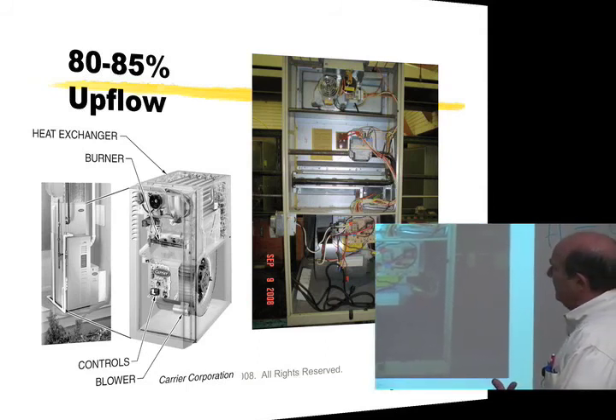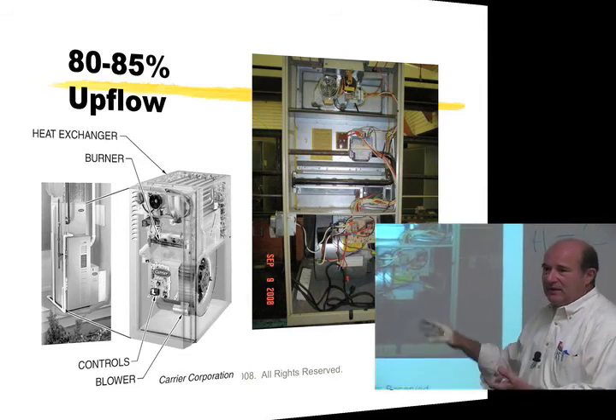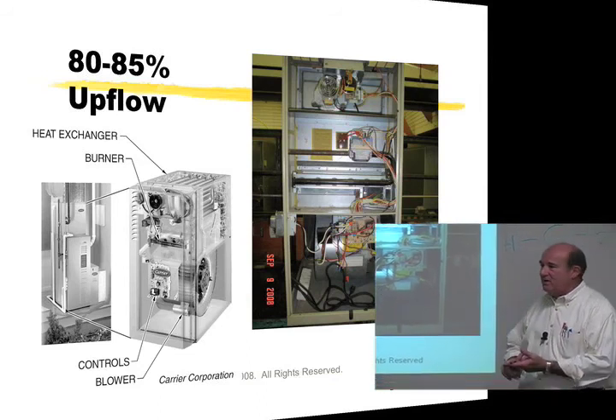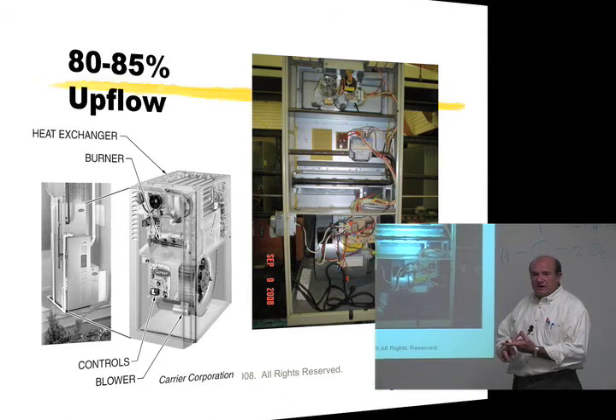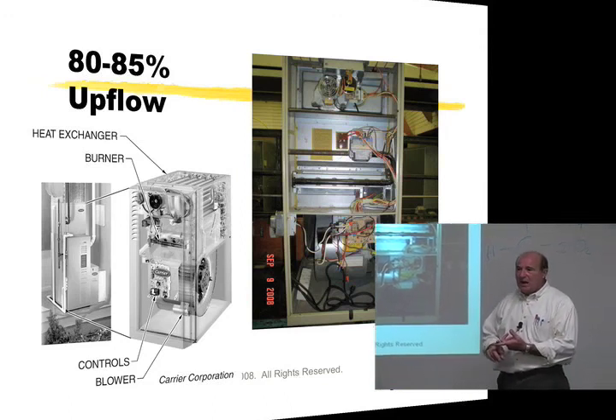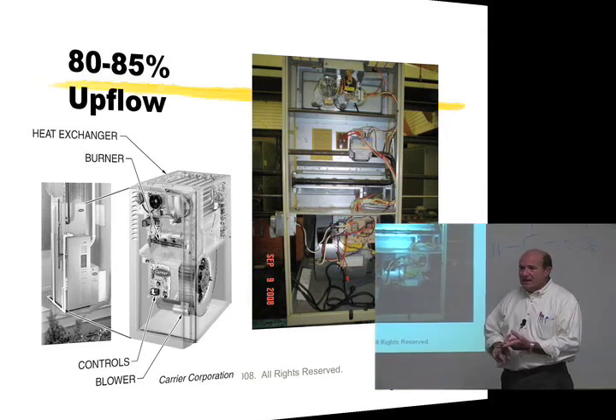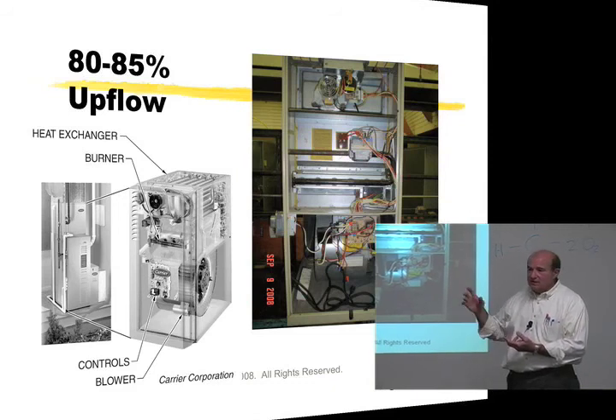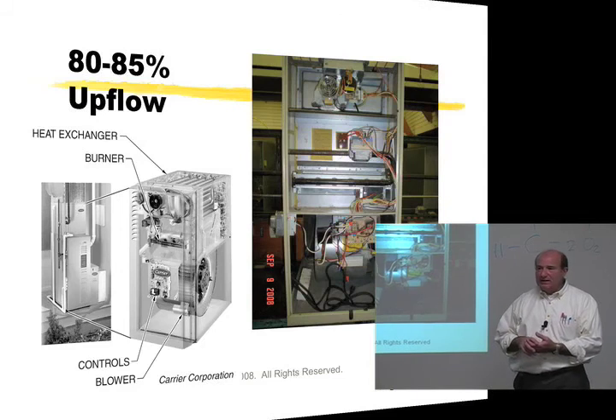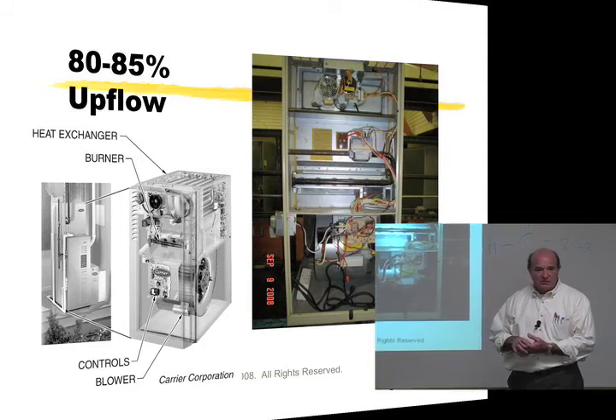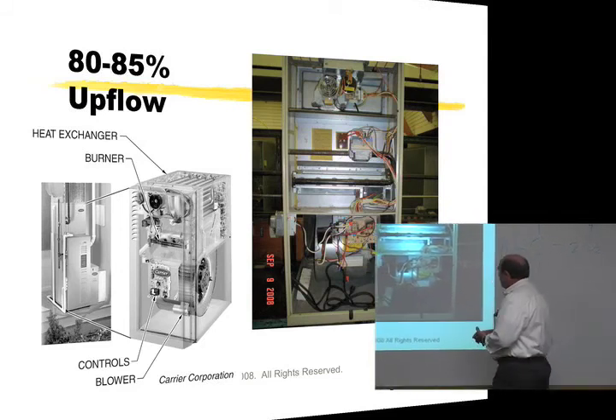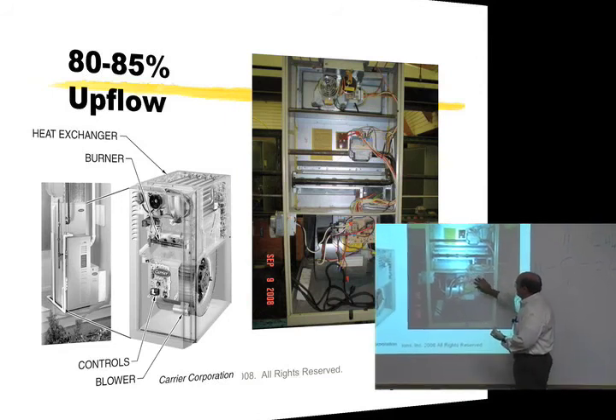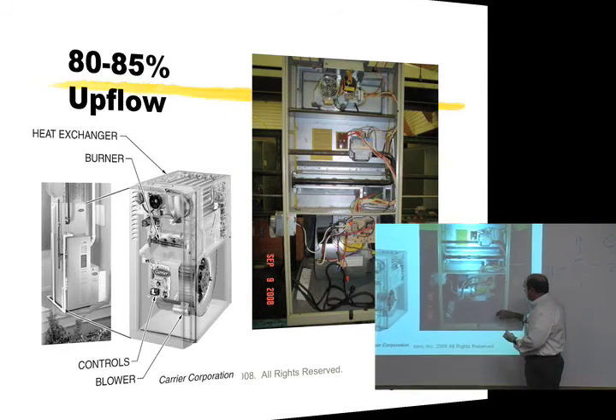Some of these, usually when we get into the higher efficiencies, but even some of the 80–85% furnaces have multiple stage gas valves. So they'll fire at a high fire or a low fire. They might turn the blower from a medium low to a medium high if we go to a high fire or a low fire. It might adjust the blower output depending upon how much gas we're using, how much we're firing that furnace. So these integrated circuit boards do a lot of different things for us.